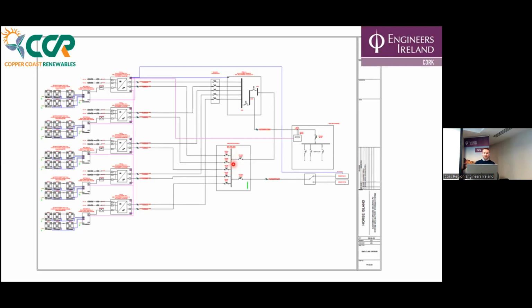Normally batteries are just for emergencies or to cover loads. So what we've done is add a cable - we changed this to be the main distribution board, fed by the 2 diesel generators. It loops out of this board back up to this board, which feeds into the existing services board. This means we can feed inverters straight in here, feed inverters straight into this board, back feed up here to come down here, and also supply a battery through here.